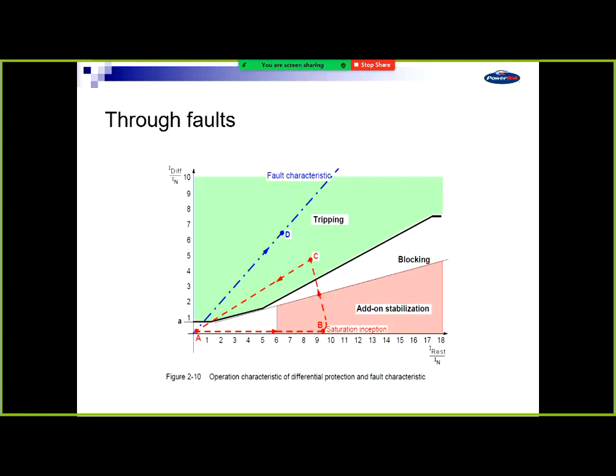It'd actually be better if that was sloped up a little bit, because your errors start to increase and it will lift up and probably be above the pickup line at 1 amp restraint, but it's in a blocking region. If the CT saturates, it would move from B to C, which is in the tripping area, but the relay says that's typical of a CT saturation, I'm not going to trip. The fault gets cleared externally and it comes back to A. So that's how modern relays can cater for a CT saturation, but they need a certain amount of good, pre-saturated current to be able to tell that it's a saturated CT, and so not trip for it. So even though it goes into the green region and trip, it won't trip.